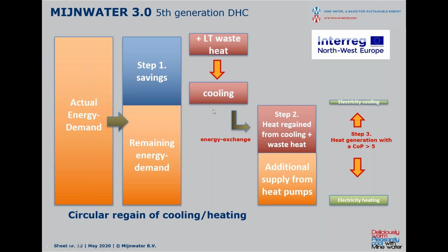If this building needs cooling, and we can reuse this cooling for heating in winter, then we add up a bit of cooling, but also find it regained in winter time as free heating energy, and add up waste energy, at best this low temperature waste energy from the city. So we reduce this remaining energy demand to more or less 30% of the original.